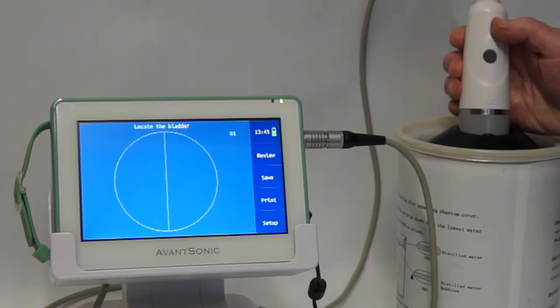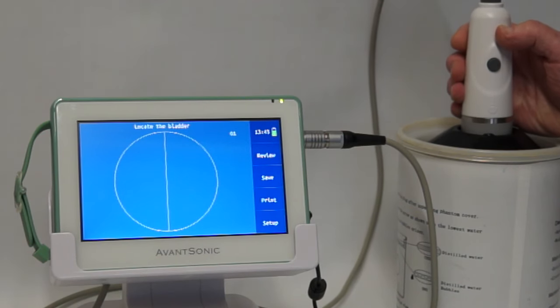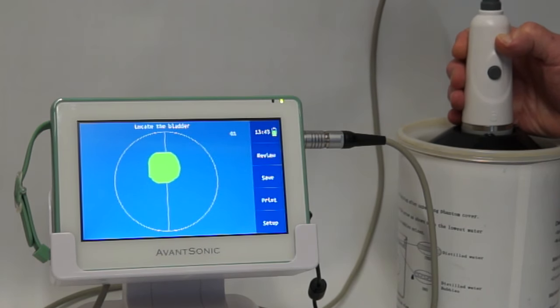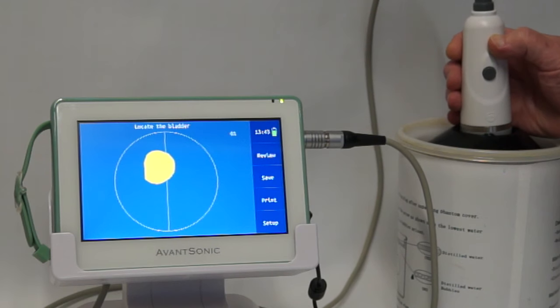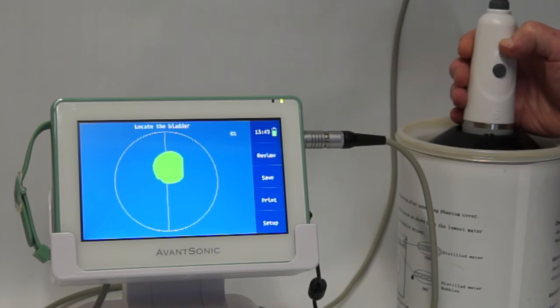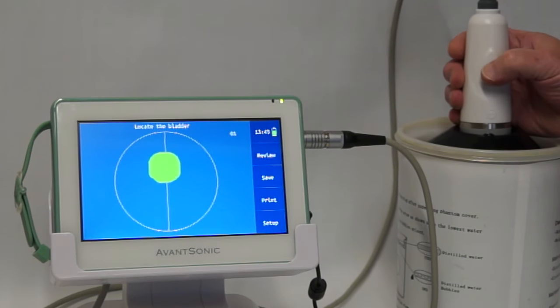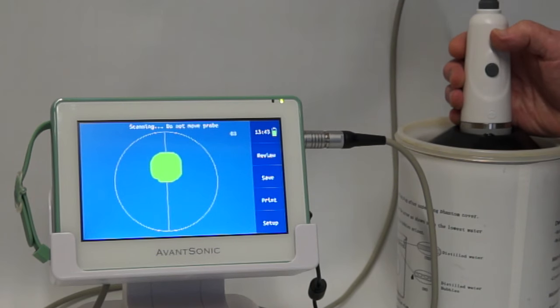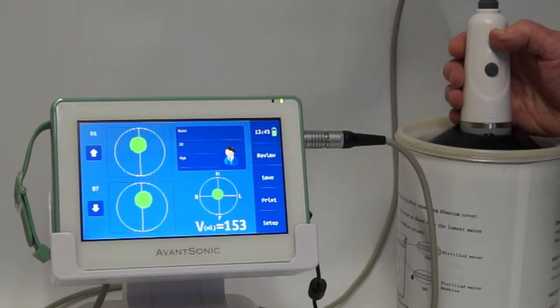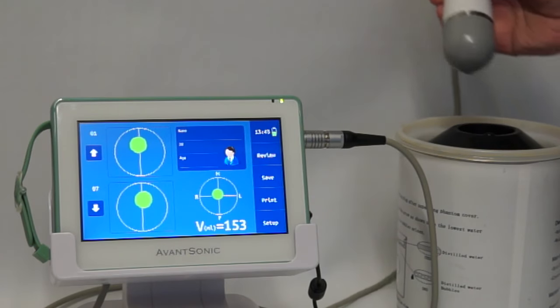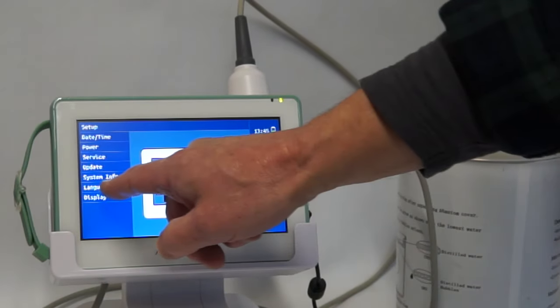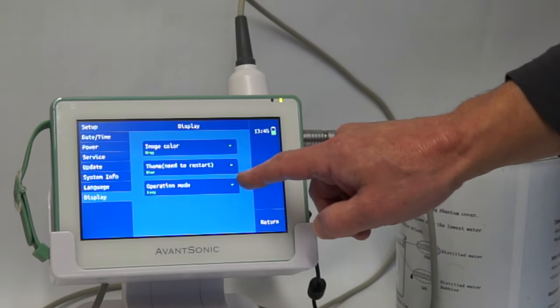By pressing the button once, we go into pre-scan mode. And you can see that as we move the scanner probe around, so the image on the screen changes from yellow to green. Press the button for the second time when you have the largest possible green image bisected by the vertical line. If you want to see the real-time image, you need to go into the advanced mode.